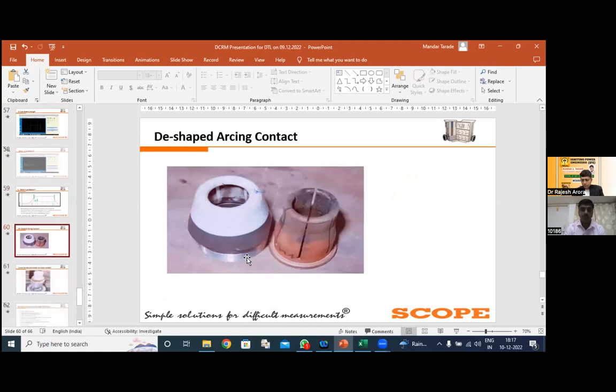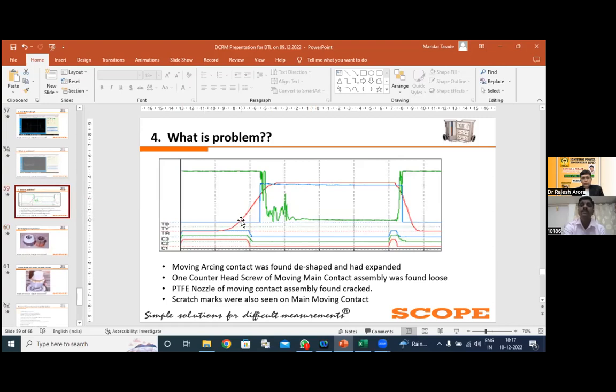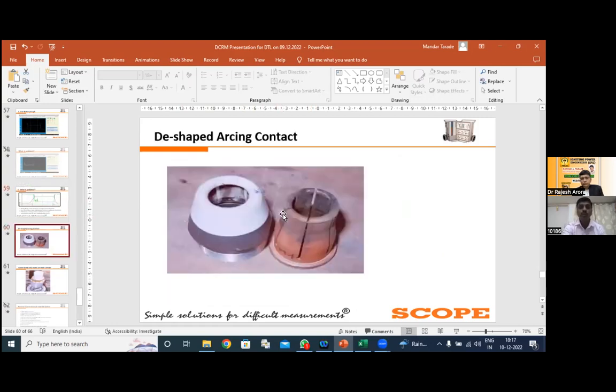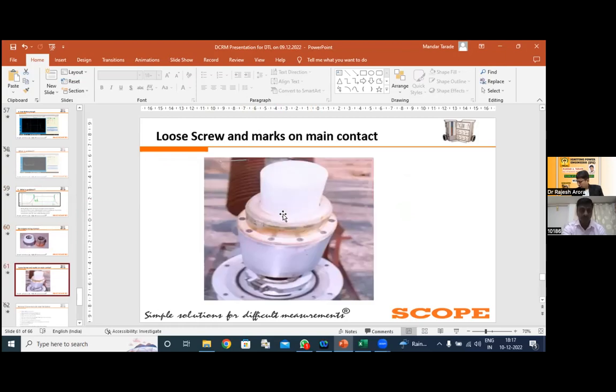Here, I will just give you the picture. It is visible on your screen. No? Yes, sir. The contact is already de-shaped, and because of that, there is a change in the resistance value of your arcing contacts, and it is significantly on the higher side. So with the help of this DCRM tool, you can comment on your arcing contact as well as the main contact.